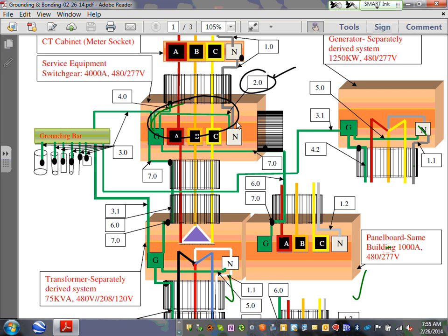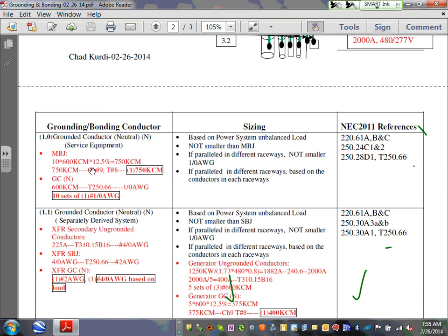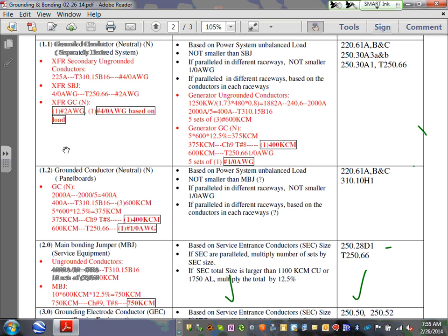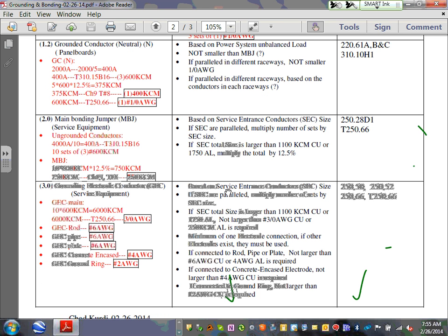It's 2.0. Can you guys see that wire coming in here? That green wire, it's called main bonding jumper. So that's number 2, the main bonding jumper. We're going to size it in a second here. So if you guys go down, Adam, here you go, 2.0. Here's 2.0. 2.0, ladies and gentlemen, is called main bonding jumper. It bonds the neutral to the ground at the service.